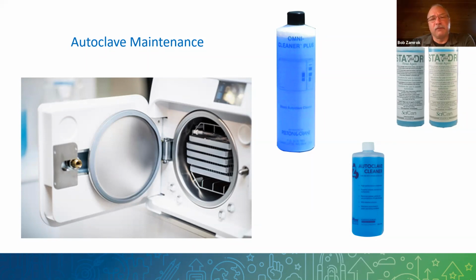Most manufacturers now have all their manuals online, with either a video or very good illustrated instructions on how to do the maintenance. It's usually pretty straightforward - most have worked at making it easy for the clinician to do it without needing someone to come in. That extends the life of your product too. Your sterilizers will last a lot longer if the internal parts are clean, no different than your dental unit.